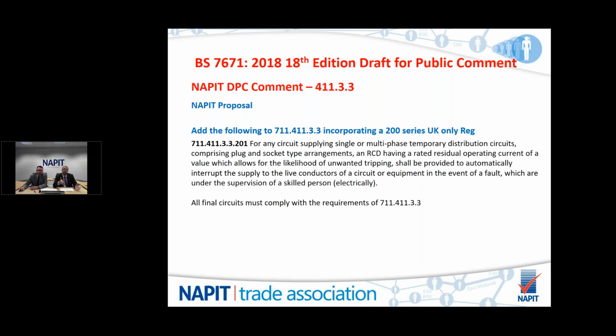The important part is that it doesn't stifle the events industry by requiring a 30 milliamp RCD on what's essentially a distribution circuit, which may then feed 10, 15, 20, 30, 40 other RCDs, which may have a build-up of leakage current and cause your main RCD to drop out in the middle of an event. Audio and events equipment notoriously have large leakage currents, and so the new regulation proposal could be a serious issue for them. So NAPIT have addressed this with this proposed new UK-only regulation, which will sit in 711 and refer to 711.411.3.3. We feel that this would help that industry greatly.